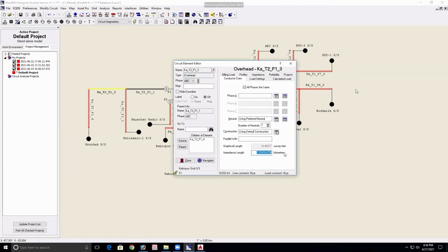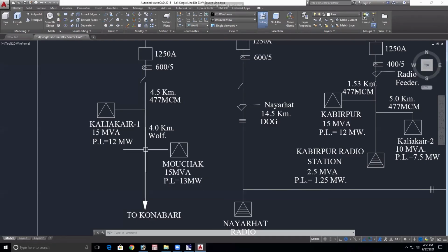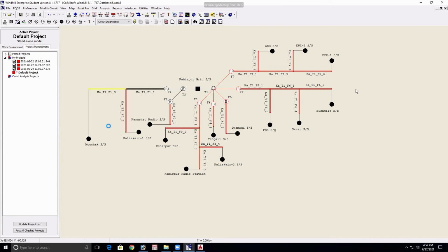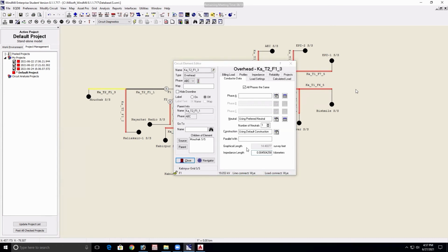So you will give it 4 kilometer Wolf, or you can give, please listen, every substation beside the line, this is without any kilometer, it's 0.09. It's a thumb rule. 0.09 kilometer. So you will put it 4.09 kilometer, directly. So you can delete these things and move these things, and you can put the value 4.09, because 0.09 is for the connections you are just giving.